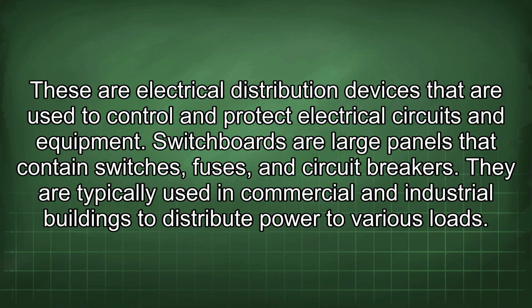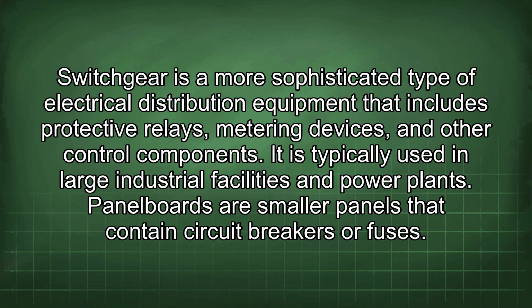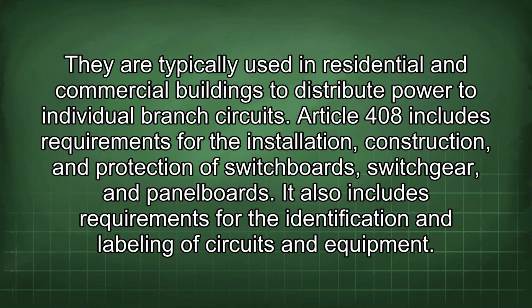These are electrical distribution devices that are used to control and protect electrical circuits and equipment. Switchboards are large panels that contain switches, fuses, and circuit breakers. They are typically used in commercial and industrial buildings to distribute power to various loads. Switchgear is a more sophisticated type of electrical distribution equipment that includes protective relays, metering devices, and other control components. It is typically used in large industrial facilities and power plants. Panel boards are smaller panels that contain circuit breakers or fuses. They are typically used in residential and commercial buildings to distribute power to individual branch circuits.